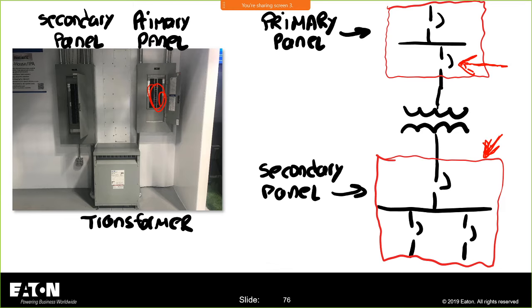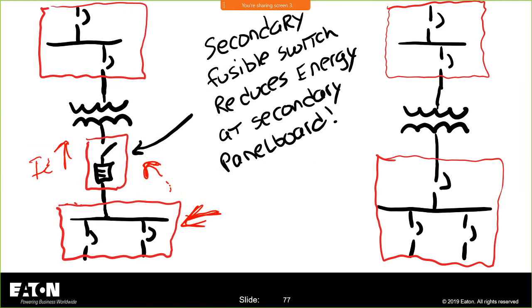So the electrical work I'm performing, the clearing time is going to be based on the upstream overcurrent protective device. So understanding where I'm at in the power distribution system helps me understand the magnitude of the hazard that I could be exposed to. Now, if I make a change, or if I look at my power distribution system a little differently, if I add a secondary fusible switch or a breaker in a box, an enclosed circuit breaker on the secondary of that transformer, now my next upstream overcurrent device is that fusible switch. And now I can take credit for that fusible switch, reducing the incident energy considerably.